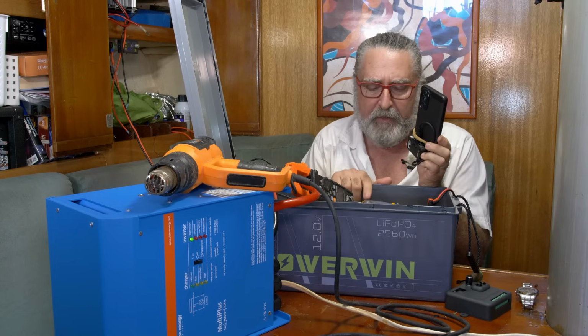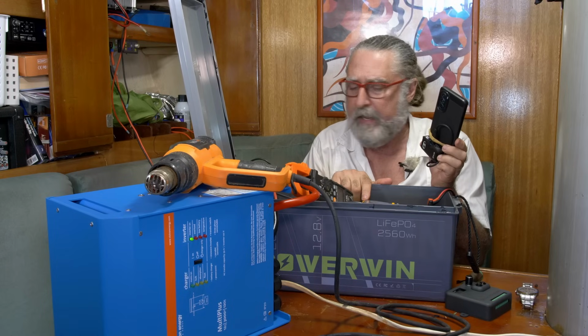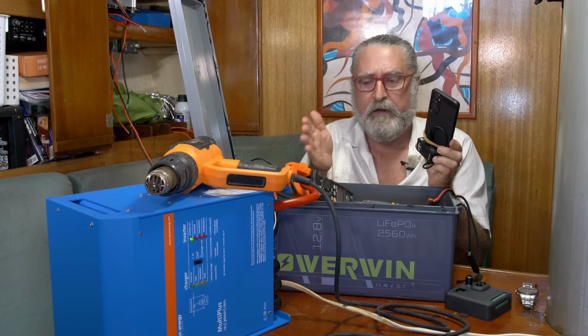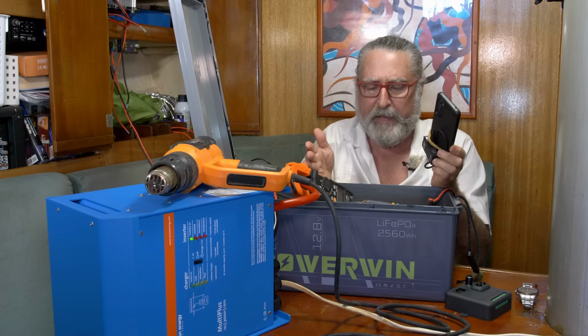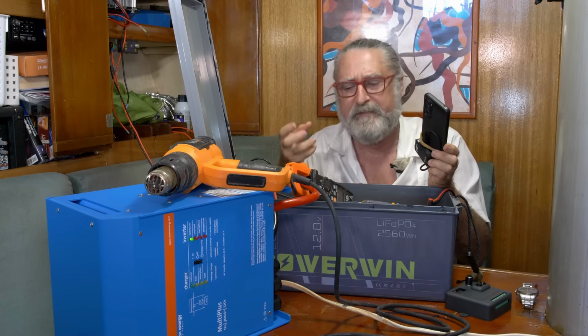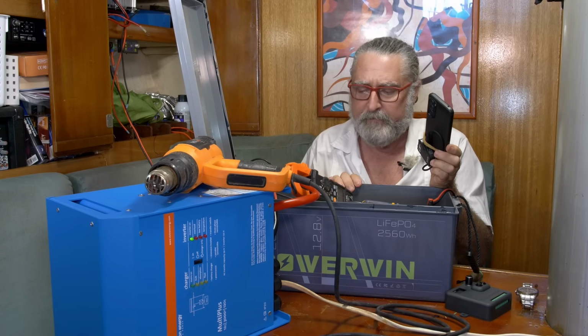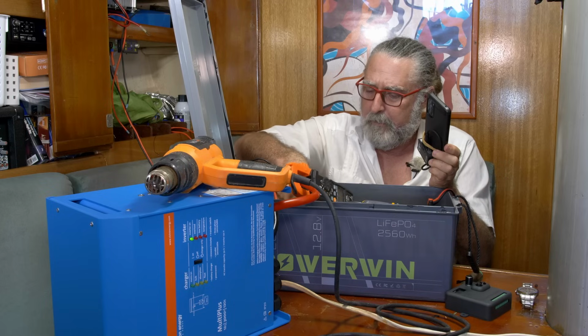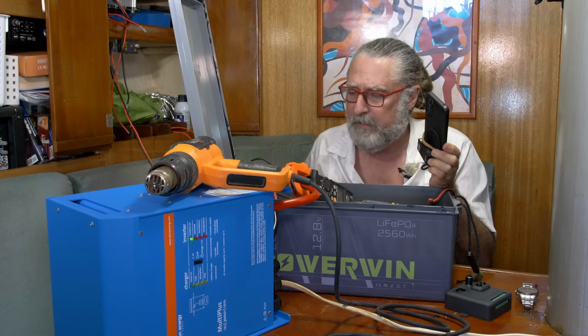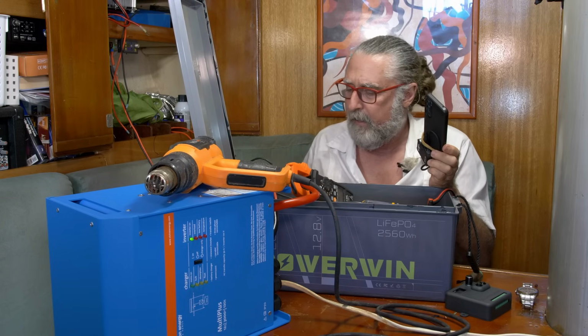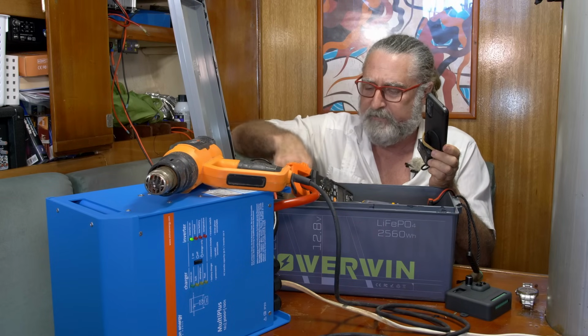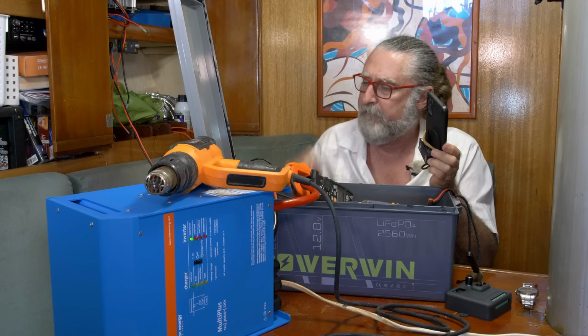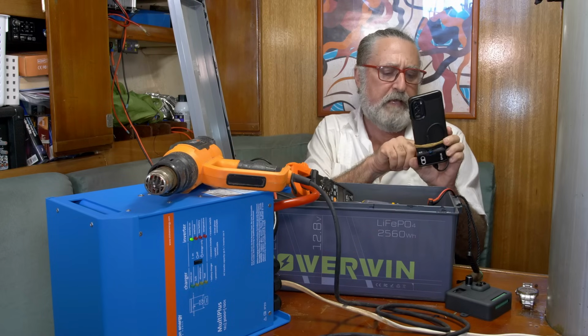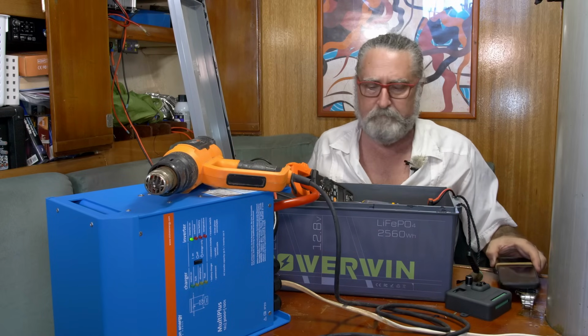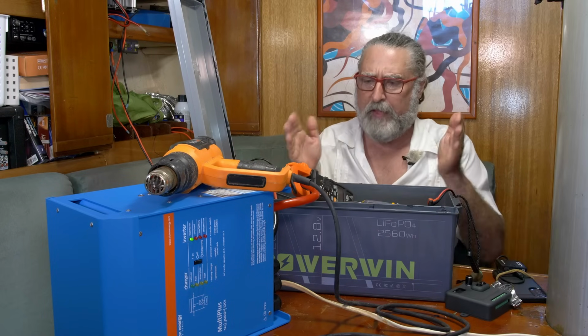This thing really is running remarkably cool, and the voltage is staying very high. But remember, we're only drawing 100 amps and it's a 200 amp hour battery, so we're only drawing at 0.5C. It's kind of, I guess, as expected, but I have no complaints. I think thermally this thing would run until it's dead. The wires are adequate to its needs. Everything's running good, so let me turn that camera off. That's it for that part of the test. Let me turn this off.